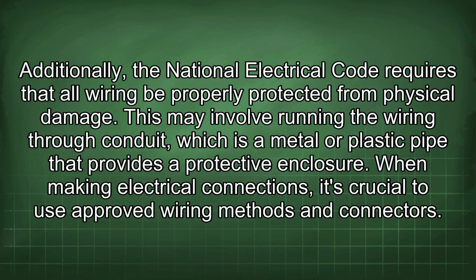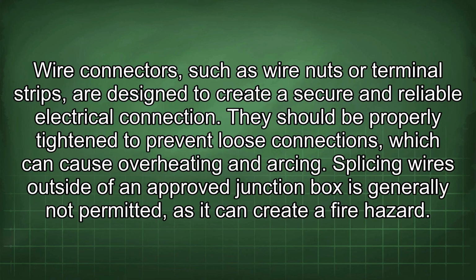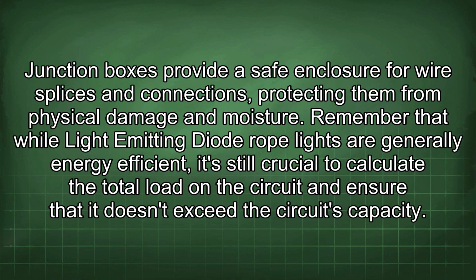When making electrical connections, it's crucial to use approved wiring methods and connectors. Wire connectors, such as wire nuts or terminal strips, are designed to create a secure and reliable electrical connection. They should be properly tightened to prevent loose connections, which can cause overheating and arcing. Splicing wires outside of an approved junction box is generally not permitted, as it can create a fire hazard. Junction boxes provide a safe enclosure for wire splices and connections, protecting them from physical damage and moisture.